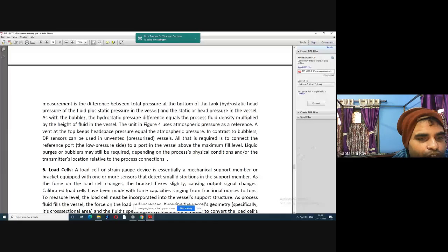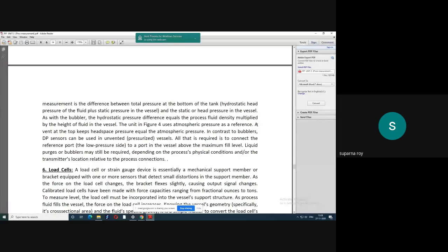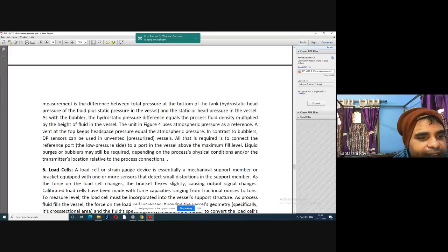So তোমাদের প্রশ্নটা একটু pressure... top headspace pressure equal to the atmospheric pressure. In contrast to the bubblers, DP sensors can be used in unvented pressurized vessels. All this requires is to connect the reference port, the low pressure side, to a port in the vessel above maximum fill level. Liquid purges or bubblers may still be required depending on the process physical conditions and or the transmitter's location relative to the process connection.